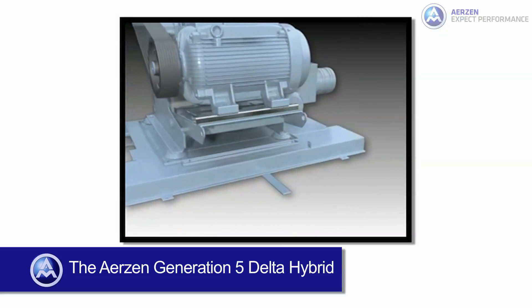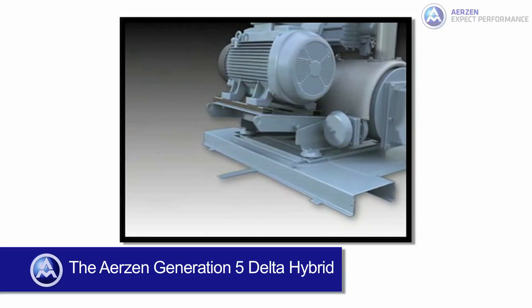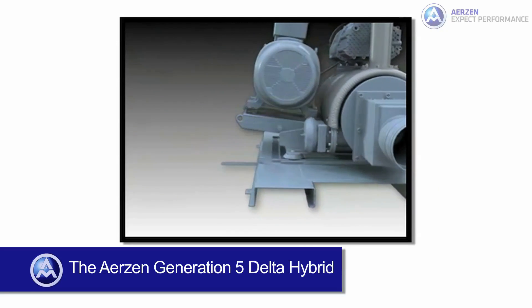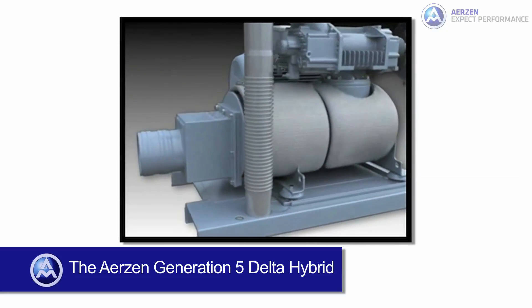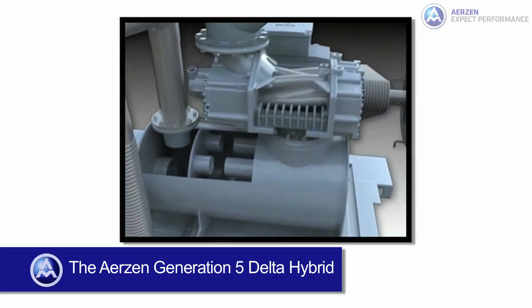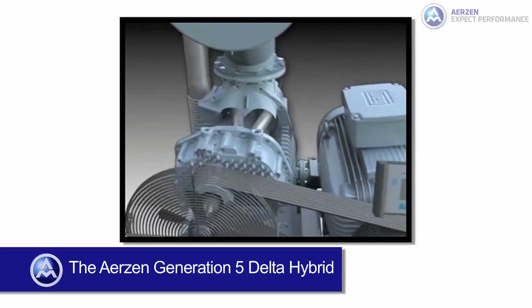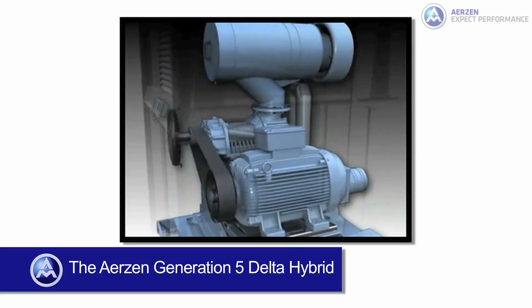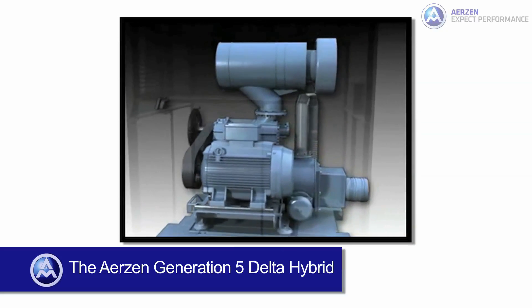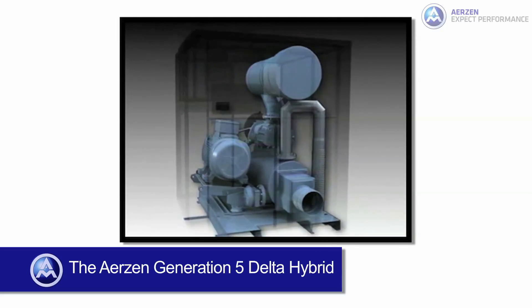The Delta Hybrid offers a very wide flow control range, from 25% to 100% with use of a VFD. The optimized fluidic design of the inlet and discharge reduces internal pressure losses. The Delta Hybrid features a high-performance automatic belt drive system, with losses under 3%. Belt drive offers the flexibility to match exactly the required airflow, even without the use of a VFD.